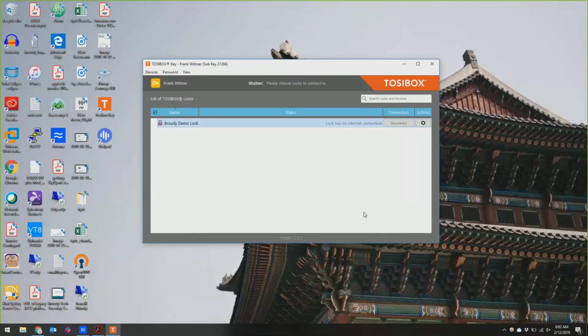Okay. And I'm assuming that all ties in with the system database and ultimately not having to build graphics for supervisors, which I can do reasonably quickly, but if I can eliminate all that work, I always like to have the graphics in the Jace as a fallback anyway. Yes. So that's the way I'm trying to operate now, is I'm working everything in our Jace here, and then once I'm done, I'll pull everything up to the supervisor through system database, and I shouldn't really have to do anything else with the supervisor. It'll pull up all my PXs as virtuals, points as virtuals, all that jazz.